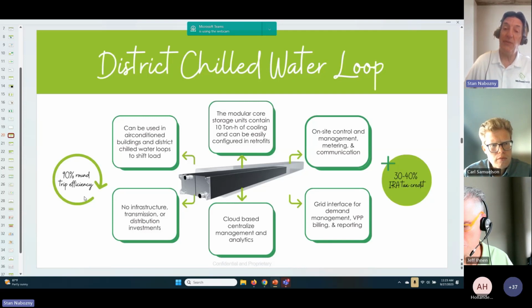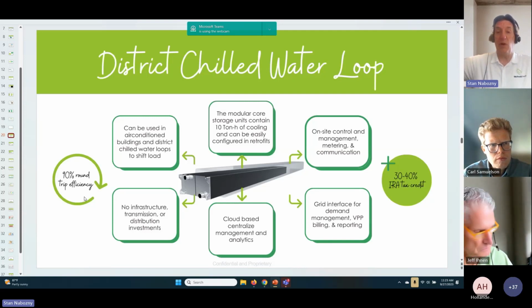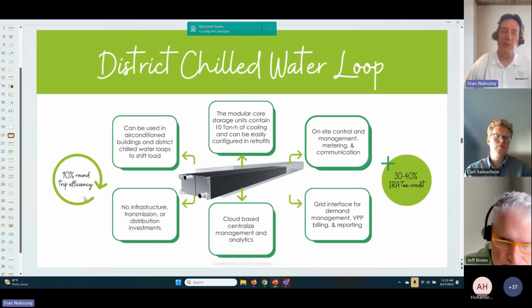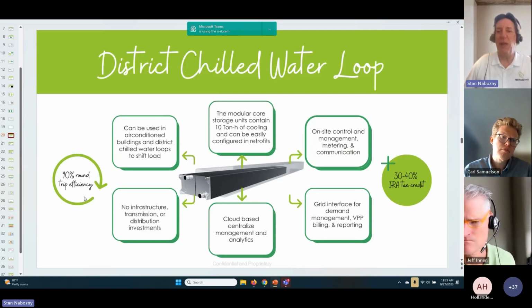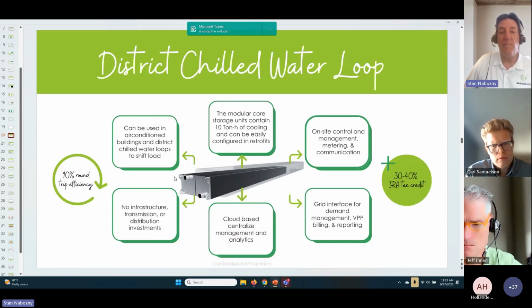There are other solutions out there that are big tanks of water - it takes time to charge a big tank of water. When you have phase change material thicker than half an inch, it takes longer for the heat to transfer in and out. These cells are a half inch, and as a result, this is a very, very efficient tool. This unit is 14 feet long by 20 inches wide by 10 inches deep.